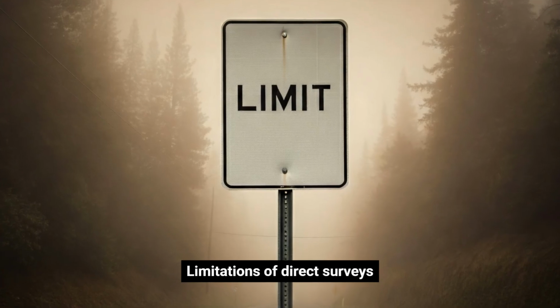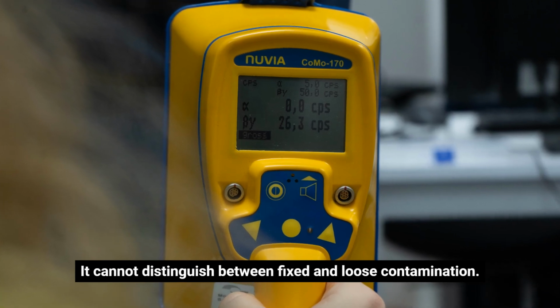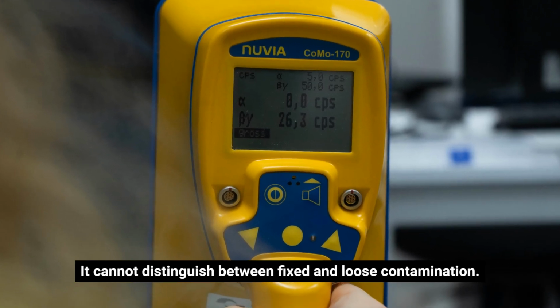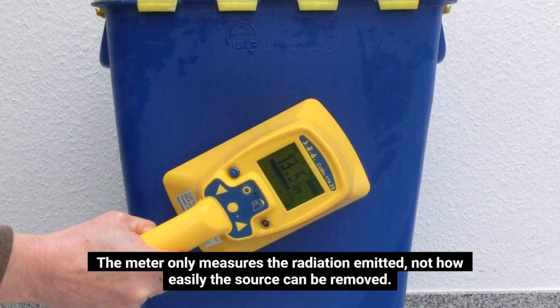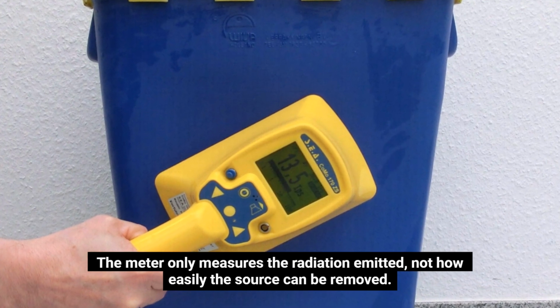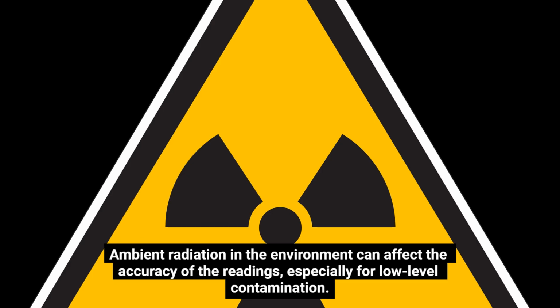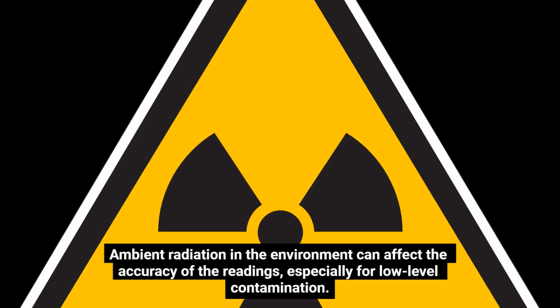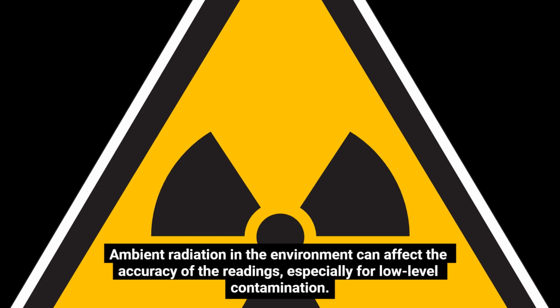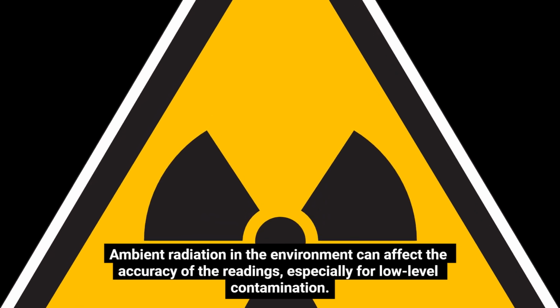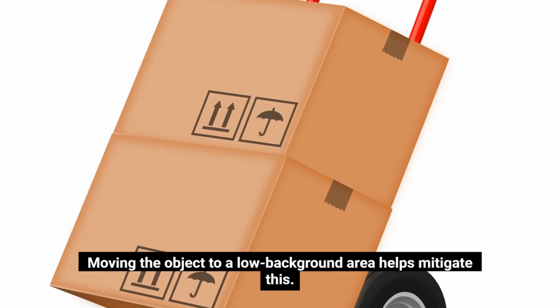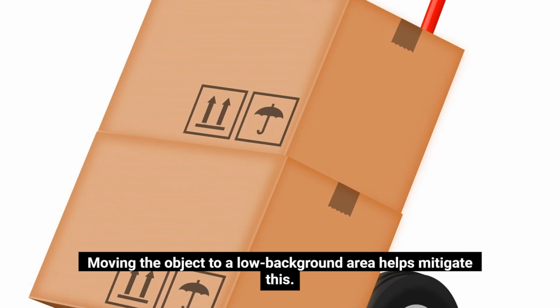Limitations of direct surveys. It cannot distinguish between fixed and loose contamination. The meter only measures the radiation emitted, not how easily the source can be removed. Ambient radiation in the environment can affect the accuracy of the readings, especially for low-level contamination. Moving the object to a low background area helps mitigate this.